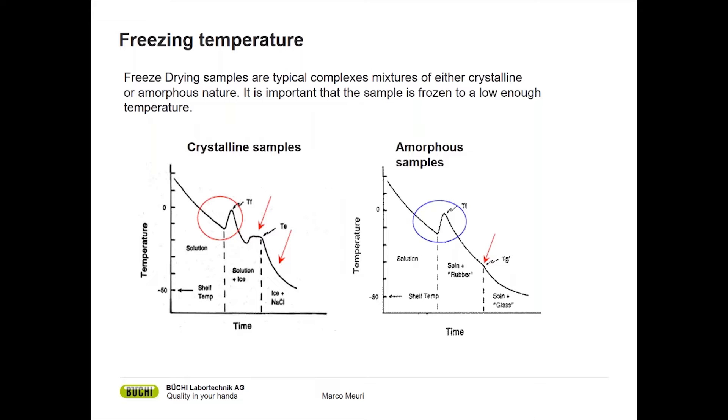But we still have some solution and we have ice. If we would now freeze dry the sample, we would start with a partly melted sample and would not end up with a nice cake of our product. So we want to cool it even further down. We see another small negative peak and a slight increase. And at that temperature, for ice and water and salt at about minus 20 degrees, this is the so-called eutectic temperature.